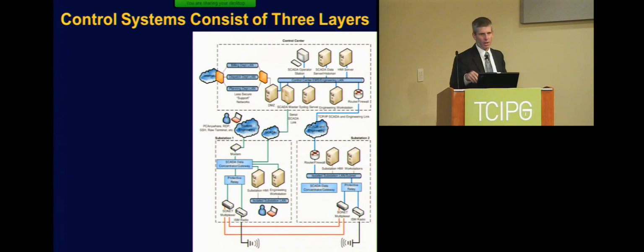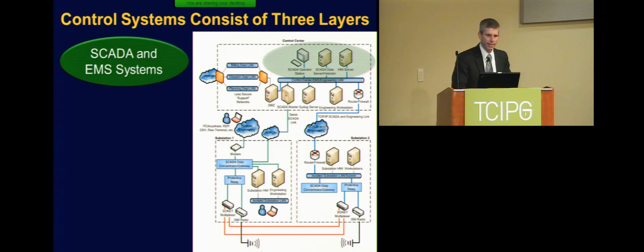I'll walk through some of the challenges we have with all the cyber inputs and outputs in our systems. Here's a typical control system notional diagram. At the top we have our SCADA and EMS system - SCADA operator stations, a historian, the HMI server, and a control network. On the outside there's a DMZ and some firewalls, though this may or may not be the case depending on the utility and their procedures.